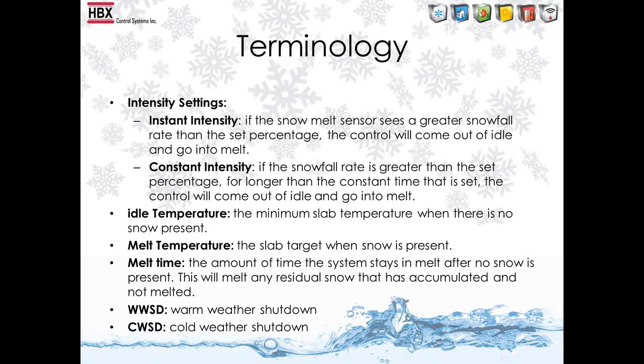And then the idle temperature is the slab target when there's no snow present. This can be either 28 degrees or 26 degrees. If people don't want to idle the slab, there's a longer recovery time. The melt temperature is the slab target when snow starts falling and the snow melt control goes into melt mode. Melt time is the amount of time that, after there's no snowfall, it will stay running to clear the slab of all of the snow. Warm weather shutdown, cold weather shutdown, we'll go over them. They're not always self-explanatory.